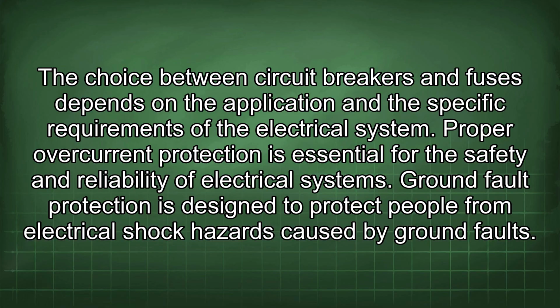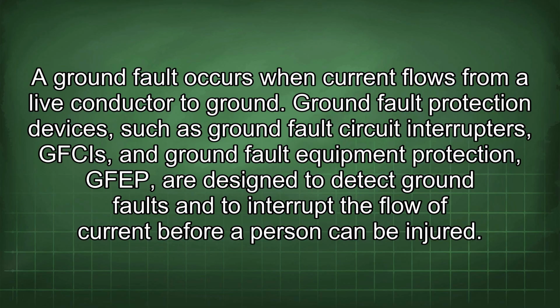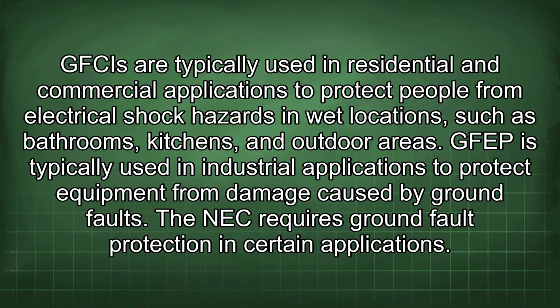Ground fault protection is designed to protect people from electrical shock hazards caused by ground faults. A ground fault occurs when current flows from a live conductor to ground. Ground fault protection devices, such as ground fault circuit interrupters (GFCIs) and ground fault equipment protection (GFEP), are designed to detect ground faults and to interrupt the flow of current before a person can be injured. GFCIs are typically used in residential and commercial applications to protect people from electrical shock hazards in wet locations, such as bathrooms, kitchens, and outdoor areas.